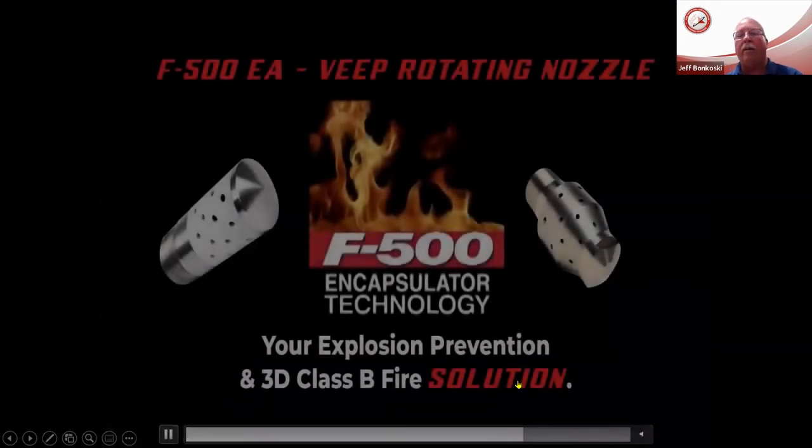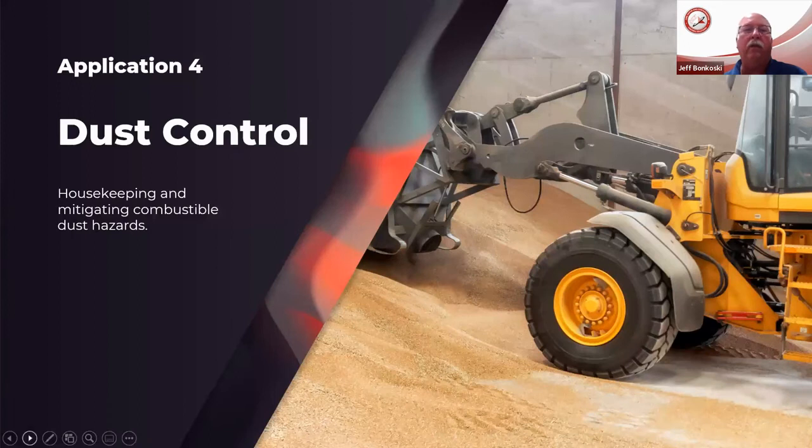But not only that, it's going to continue as long as that system is flowing. It's going to continue to encapsulate those vapors, preventing them from finding an ignition source and flashing back. So you have time now to go into safety shutdowns, or shut off valves, or take the actions that you need to stop the flow of the gas or the liquid that potentially could be responsible for the explosion and fire. You can set off those safety devices and prevent that fire and explosion from ever occurring.